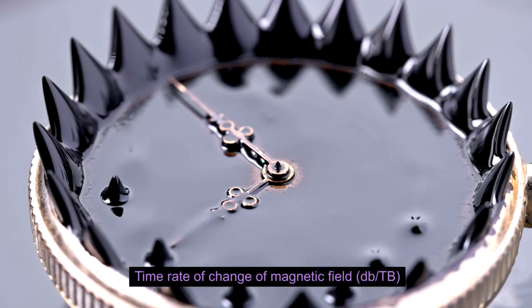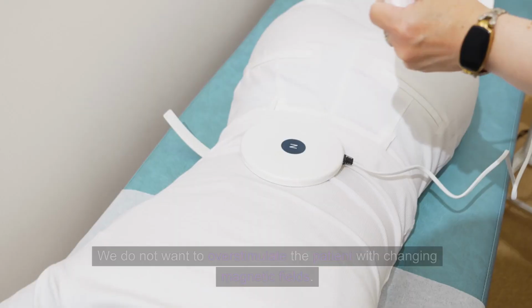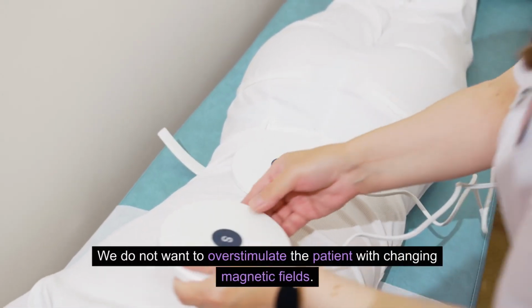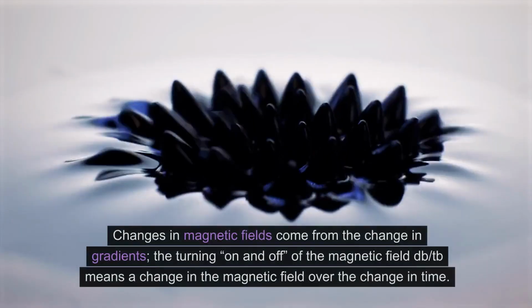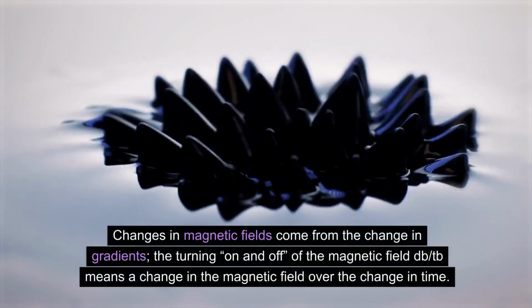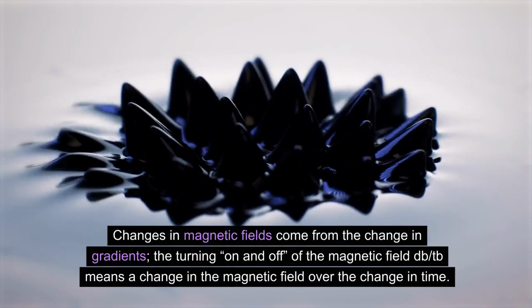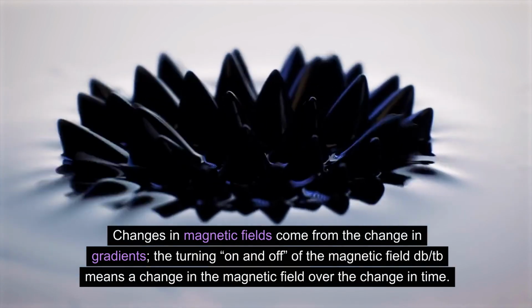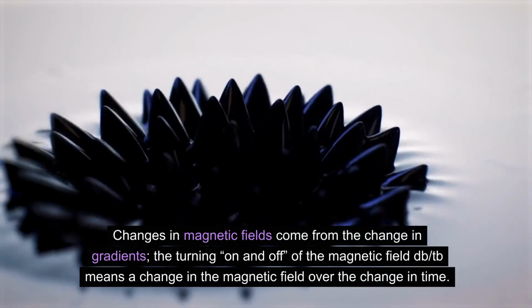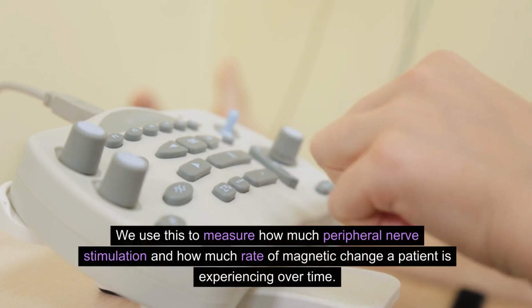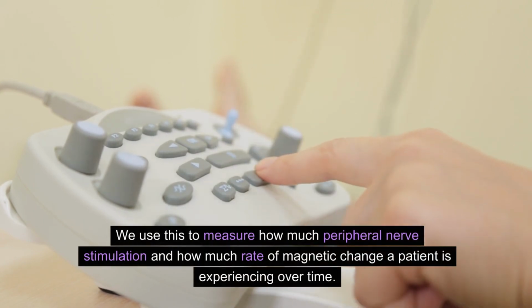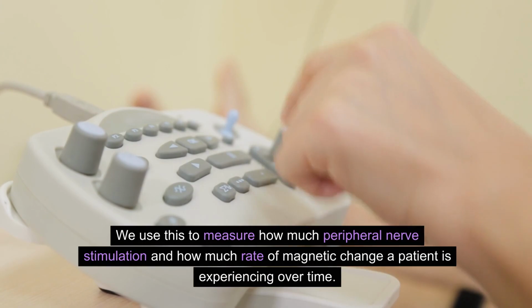Time rate of change of magnetic field, dB/dt. We do not want to overstimulate the patient with changing magnetic fields. Changes in magnetic fields come from the change in gradients, the turning on and off of the magnetic field. dB/dt means a change in the magnetic field over the change in time. We use this to measure how much peripheral nerve stimulation and how much rate of magnetic change a patient is experiencing over time.